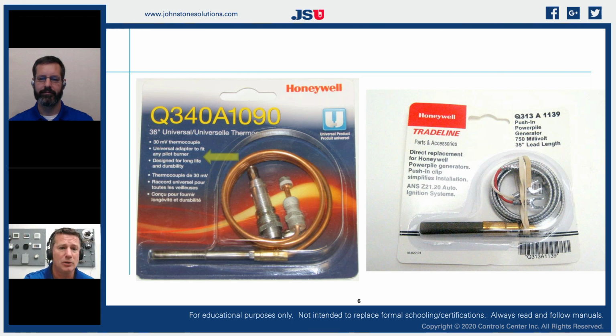So if we look at a standard thermocouple, 30 millivolts, right? So we take that same philosophy and we need to hold a larger valve open, one that has a larger solenoid on the gas valve. We simply increase the amount of thermocouples that were inside of that so that it now is a thermopile that can produce more voltage. So with that typical thermopile, if we look at that Honeywell Q313, that one produces 750 millivolts. So typically in the residential world, we're working with gas valves that are moving under 200,000 BTUs. So we're typically on a gas valve that 30 millivolts is sufficient to hold that valve open.